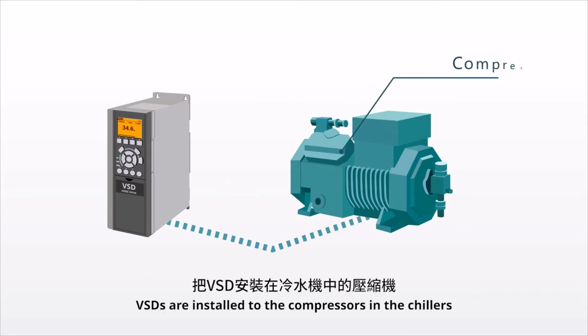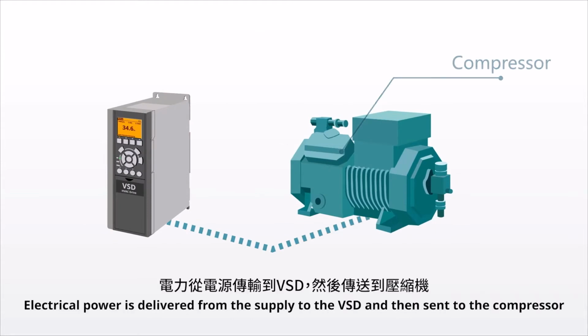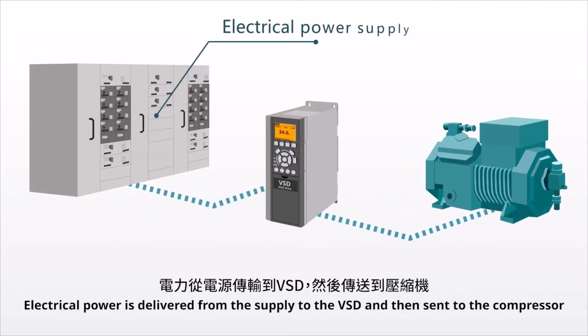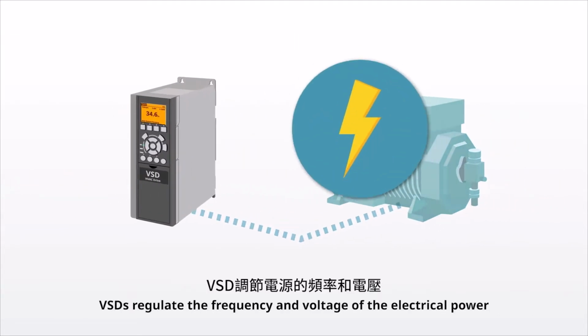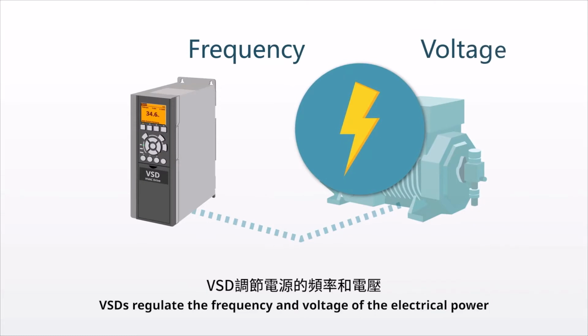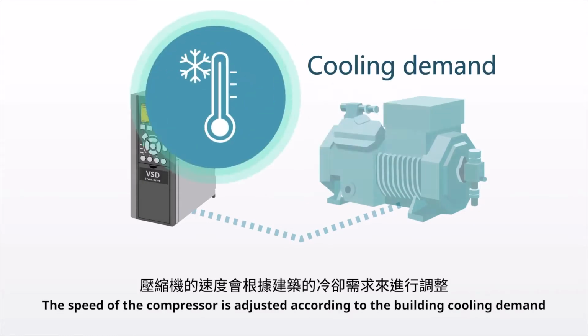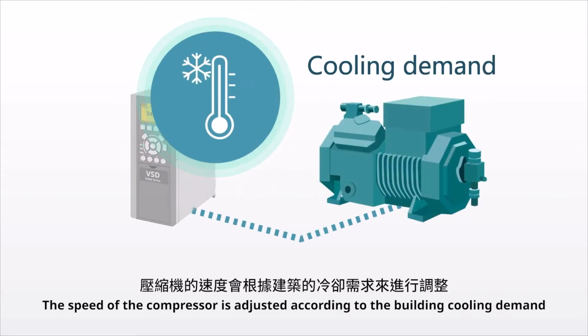VSDs are installed to the compressors in the chillers. Electrical power is delivered from the supply to the VSD and then sent to the compressor. VSDs regulate the frequency and voltage of the electrical power. The speed of the compressor is adjusted according to the building cooling demand.